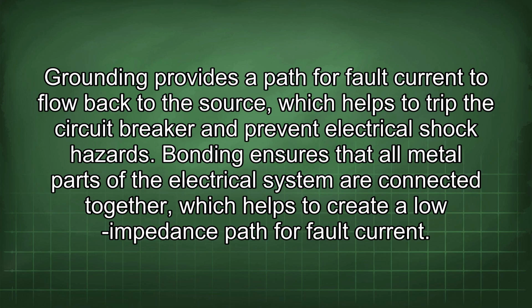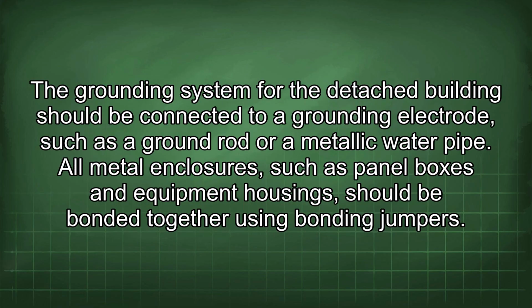Bonding ensures that all metal parts of the electrical system are connected together, which helps to create a low impedance path for fault current. The grounding system for the detached building should be connected to a grounding electrode, such as a ground rod or a metallic water pipe. All metal enclosures, such as panel boxes and equipment housings, should be bonded together using bonding jumpers.